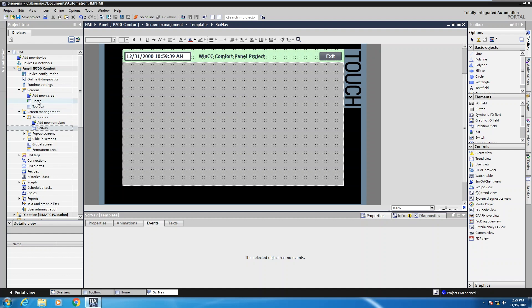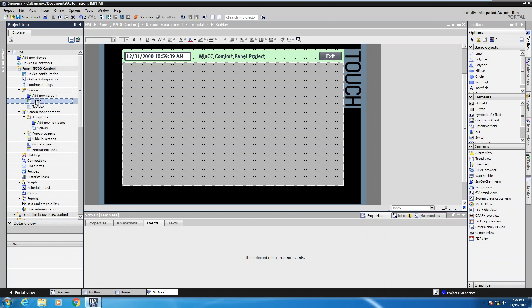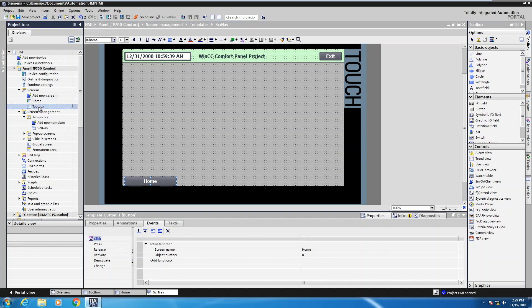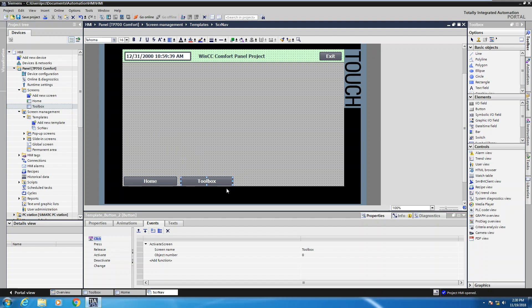I'd like to take the home screen from my project tree and drag it onto this template, positioning it in the lower left-hand corner. That will give me a button that already has the function to navigate to that screen. I can also drag the toolbox screen onto the template. Each button now has the activate screen function already assigned — toolbox for the toolbox button and home for the home button. That's how you would manually switch screens: you pick the activate screen function and assign it to a button event.